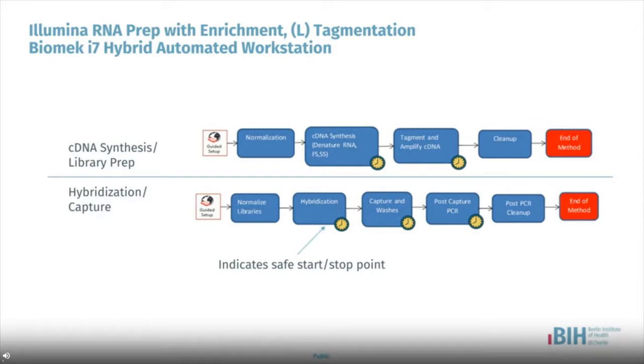The method is divided into two separate workflows: cDNA synthesis and library prep, and hybridization and capture enrichment. The method is written to allow users to select their given start and stop points, which coincide with Illumina's published safe stop points, represented by a yellow clock icon. At the start of each workflow, a guided lab work setup assists users with a graphical interface showing how to set up the run, specifying number of tip boxes needed, required labware, and minimum reagent fill volumes. This is a dynamic interface that changes depending on user-defined run parameters.